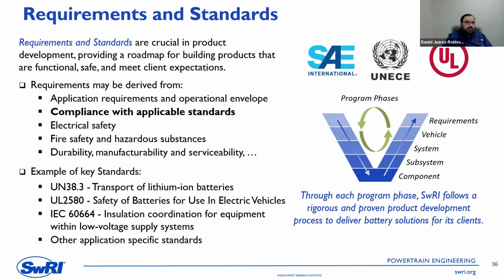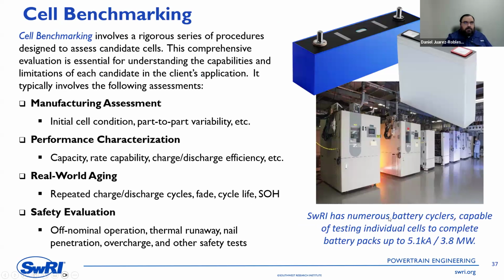We have all the requirements to test that. To start, we test all the different standards, UN, UL, IEC, going from cell level up to battery level. We can test cell-to-cell variation, characterize capacity, charge and discharge resistance and efficiency, and test real conditions, not only CCCV charge and CC discharge, but also applying drive cycles into some of these large cells.